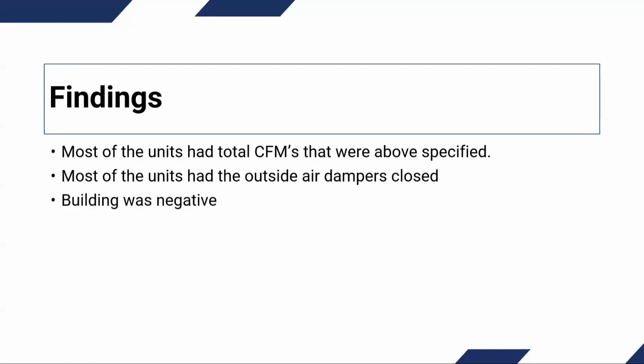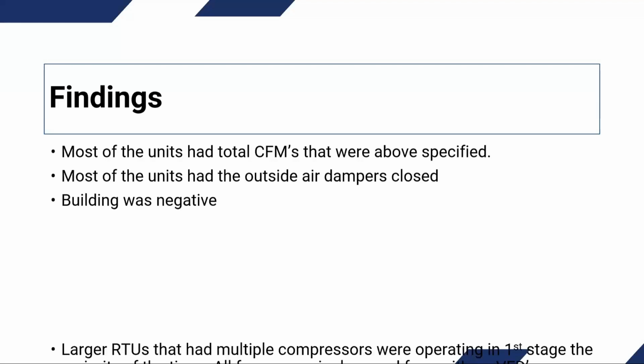So the building was negative since the outside air dampers were closed, which again, like I mentioned earlier, the outside air is typically our main cause for humidity concerns. And whether it's being brought in through doors or the equipment, the outside air is going to come into the building.